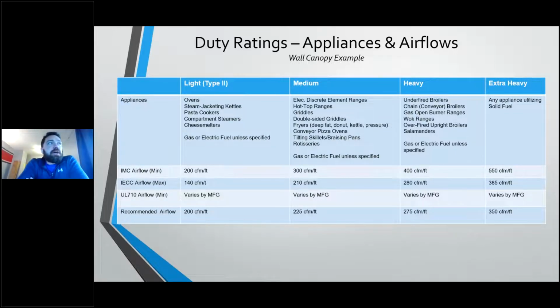So now I know, and then the rest of that 20% would be accomplished through transfer air, keeping a kitchen in a slightly negative standpoint. So now that I know my design CFM, I know that I'm going to have, let's say, a 10-foot hood. It's going to be 275 CFM per foot, so it's going to be 2,750 CFM, and 80% of that is going to be supply. It's going to be what my supply is going to be.